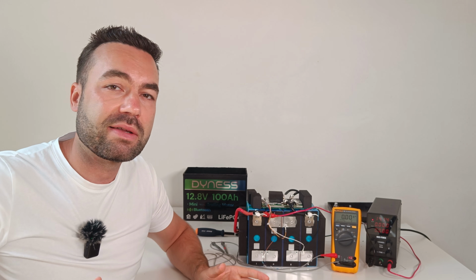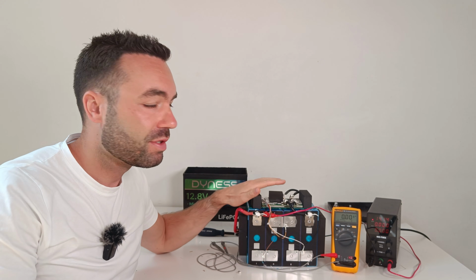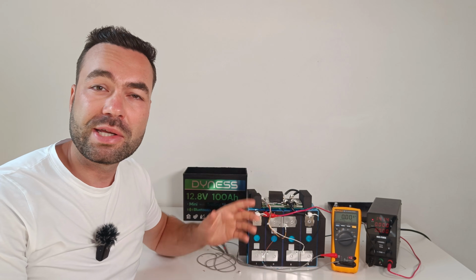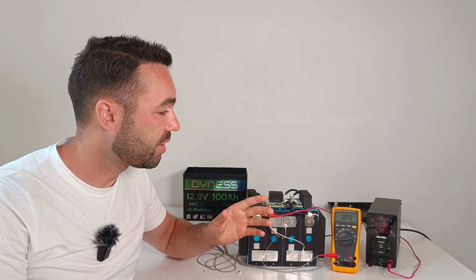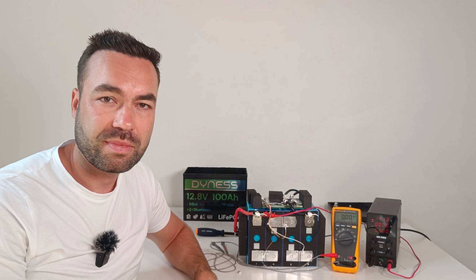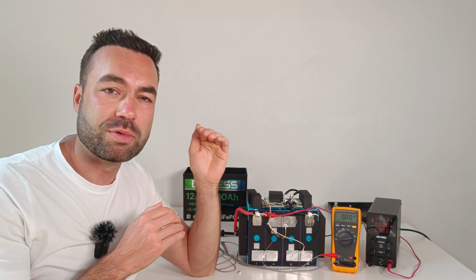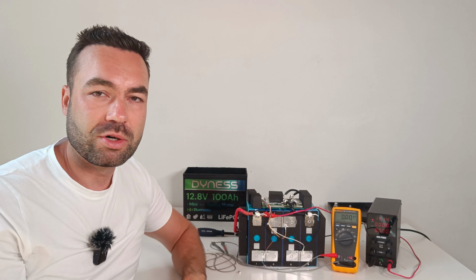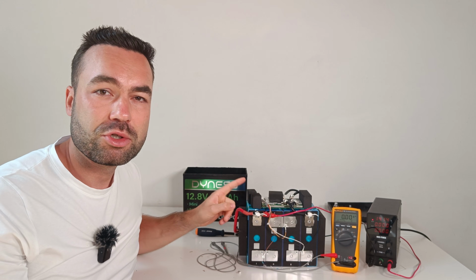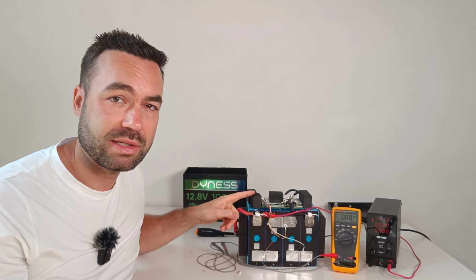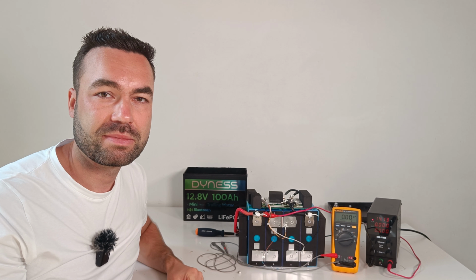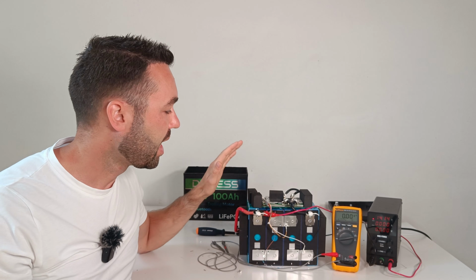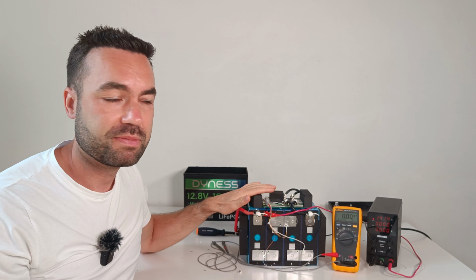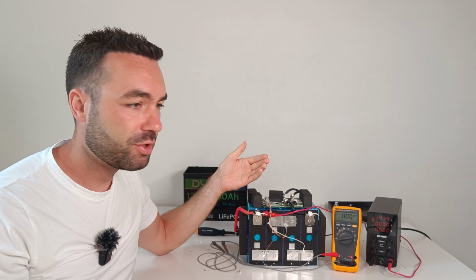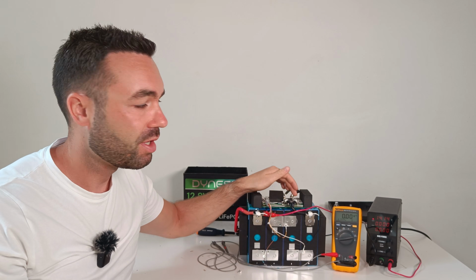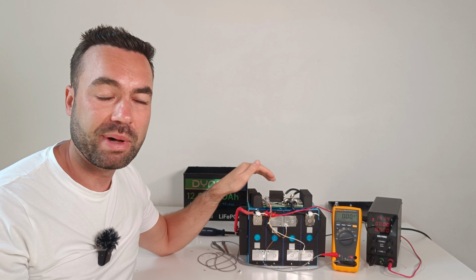It's a setting inside the BMS that can be enabled during programming. I really don't understand why manufacturers don't turn this on. Every time the battery reaches absorption or the current drops below 1 amp, the BMS should be balancing, but this one isn't, and I really don't get it. So for that reason alone, I cannot recommend this battery. It's an improvement on their previous version with a higher balancing current, but they need to enable the balancing when not charging.